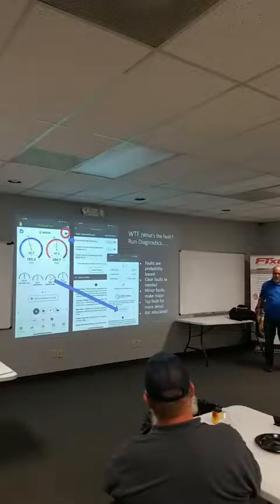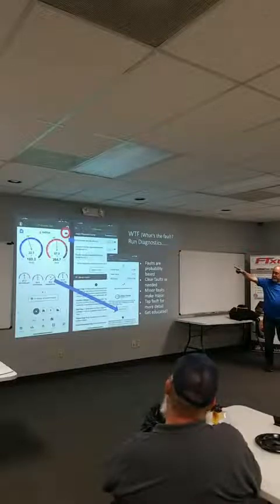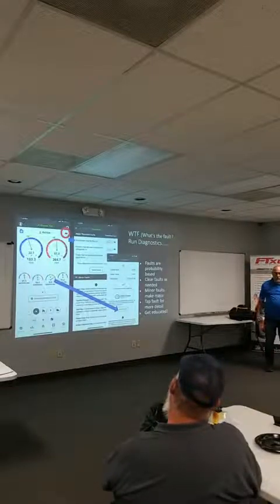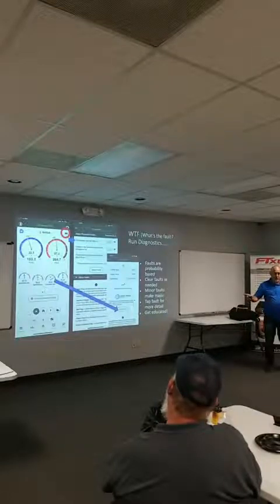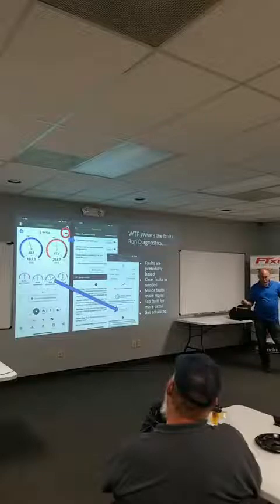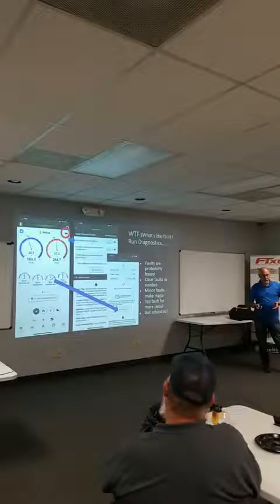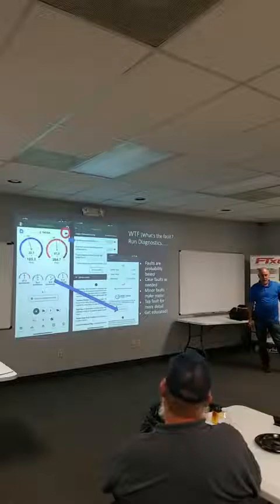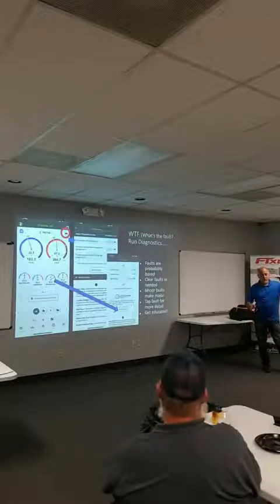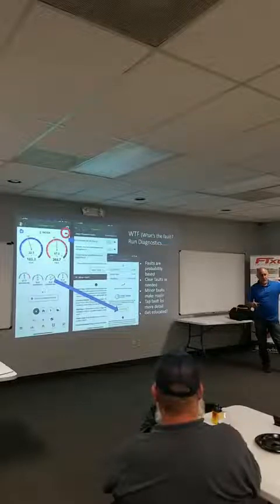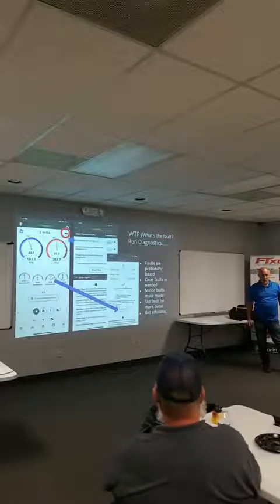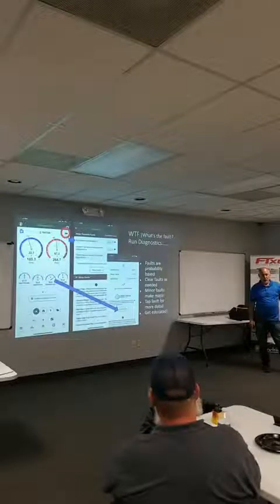We use what's called the Bayesian mathematical model, and basically Bayesian is part mathematical and part common sense, right? So when you look at this, both scored a 2, but the condenser is scoring higher on the fault because the odds are higher that you have a dirty condenser than a refrigerant overcharge, right? If you looked at all the faults in our industry, which I just did the other day, I pulled down somewhere around 60,000 records out of Measurequick. I have data on every system in the country that people use Measurequick on, and what I do with it is go through and look at how systems are running so I can make our software better. A lot of it's all done by hand because I don't have artificial intelligence to do this. I've got to use my own, right?